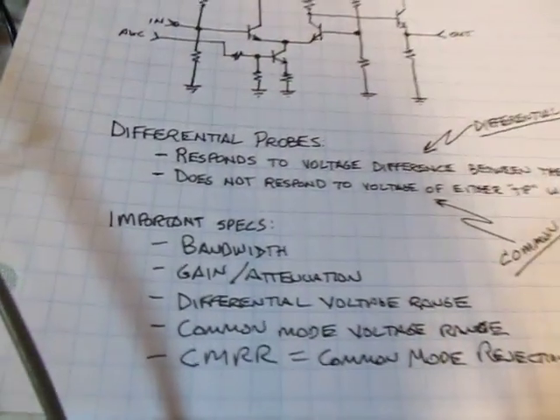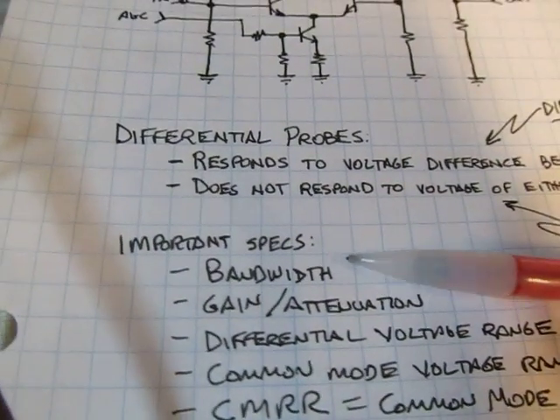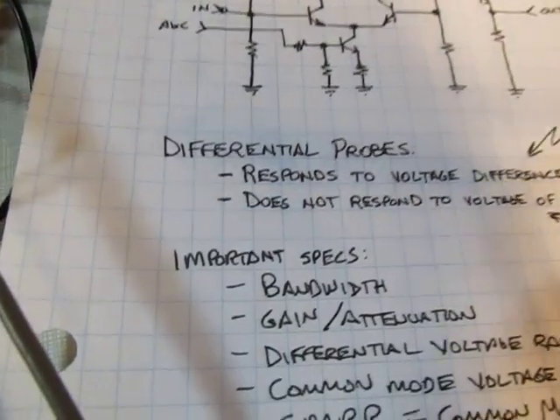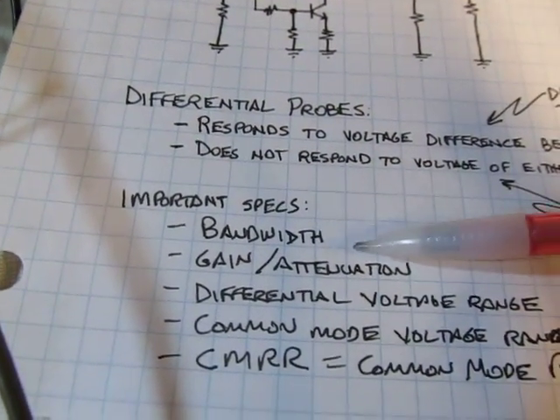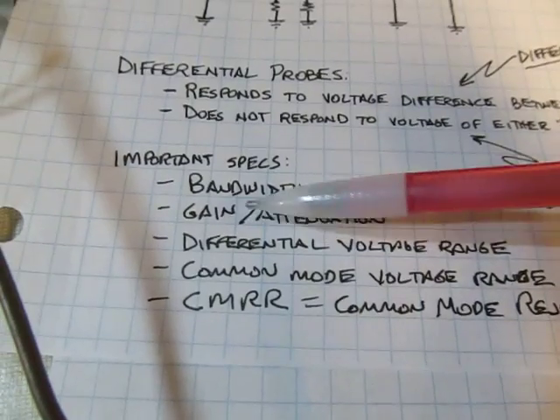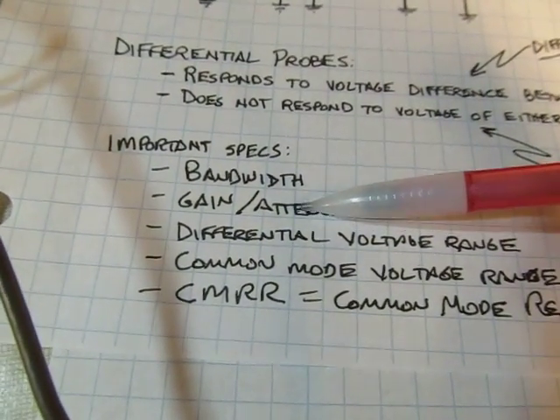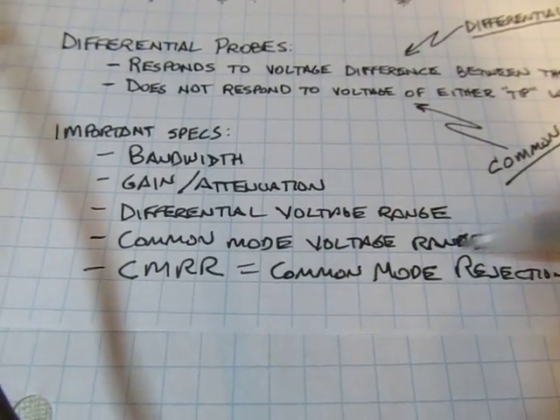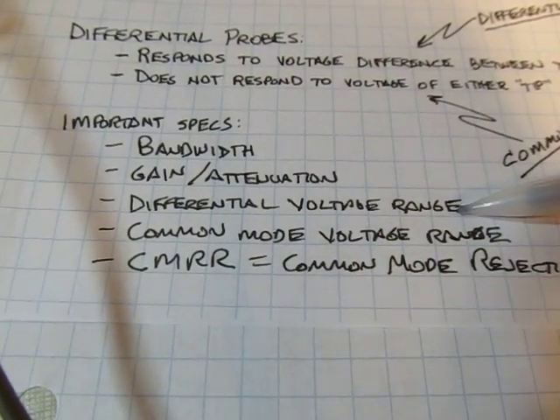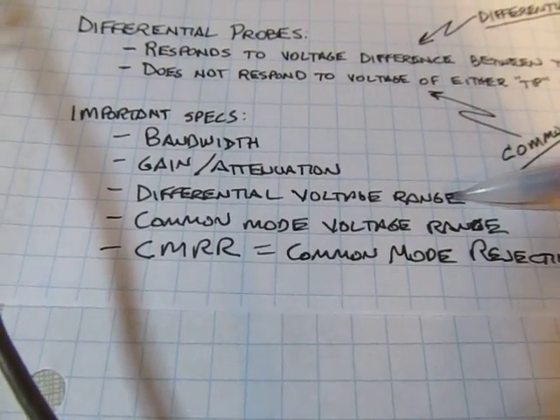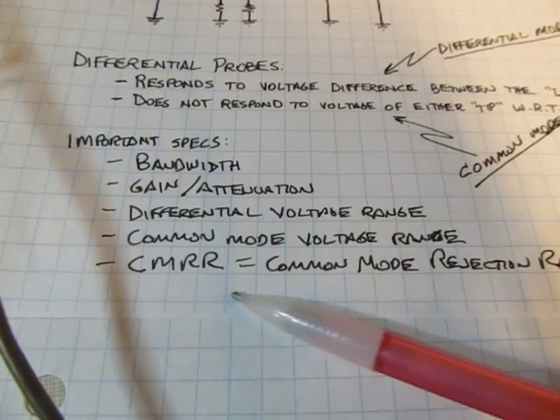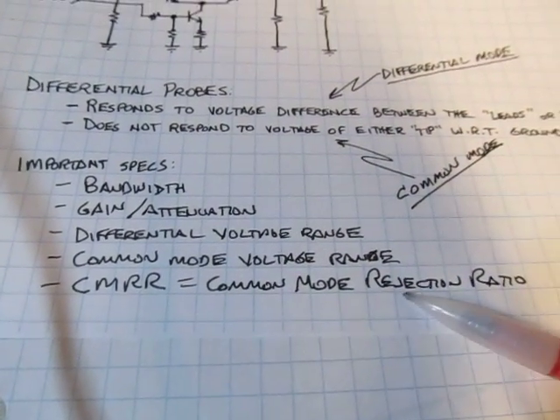One more thing to think about is some important considerations with differential probes. Obviously, bandwidth is a big consideration. It is an active probe. So you do have to worry about what its bandwidth is and also some other considerations. The probe is going to have either some gain or attenuation associated with it. You also have to take care to look at what the differential voltage range and the common mode voltage range is for the probes to ensure that in your application you don't exceed either of those. Then there's one more parameter which is kind of important. It's called the common mode rejection ratio.